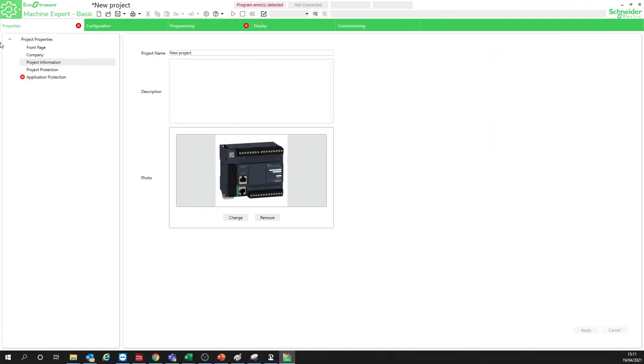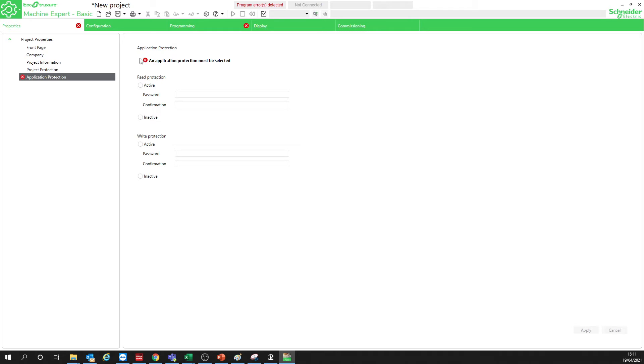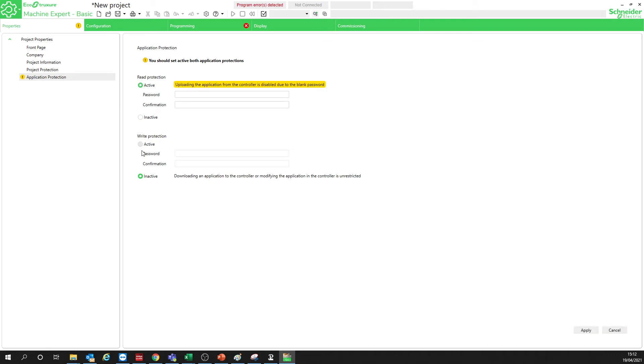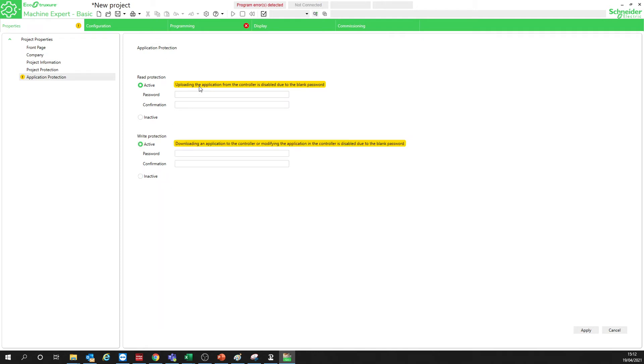So let's go back to the software. By default, you have a red cross here — you need to select one of these options. You can select Inactive in both if you want, and you'll see this warning. If both are set to Inactive, it says uploading the application from the controller is unrestricted — so everyone can read from and write to the controller.